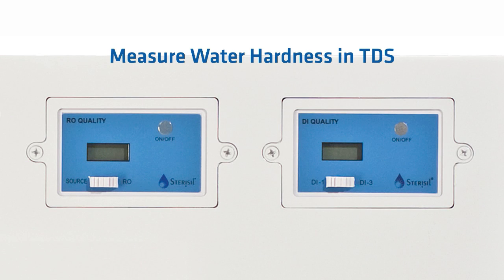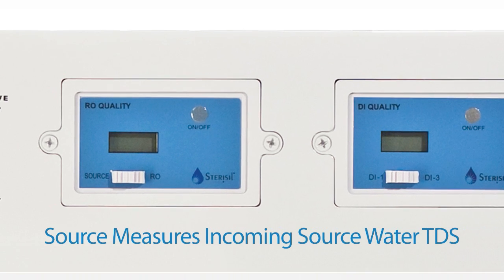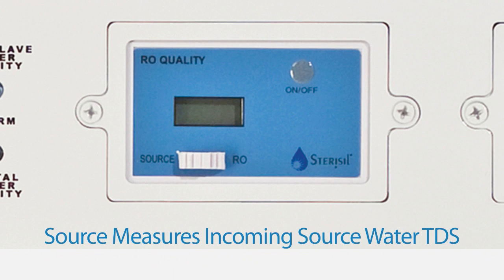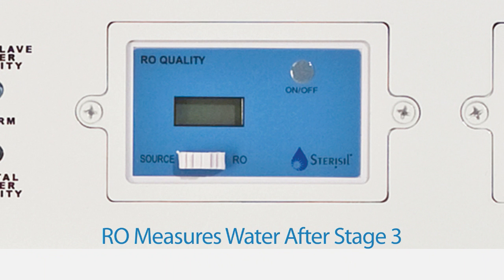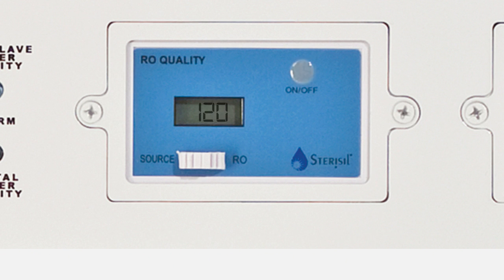This monitor must be reset when a new set of cartridges is installed. The first blue monitor is used to monitor the hardness of the water in parts per million TDS of the water that is entering the system and the water that has been treated by the first 3 cartridges. The power button is in the top right-hand corner of the monitor panel. To switch between the source water reading and the RO water reading, move the white switch from left to right. This monitor can be used to troubleshoot the system.